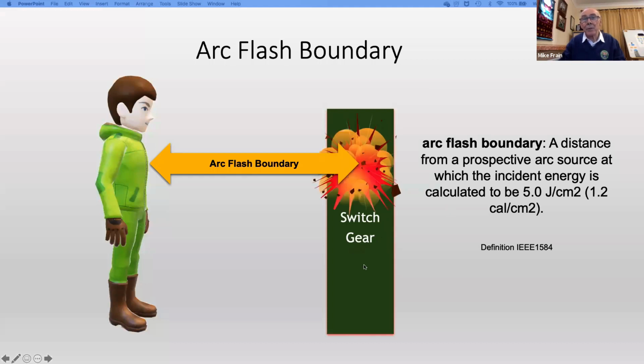And then I mentioned arc flash boundary. What's this? This is quite a good and important measurement, actually. From IEEE 1584, an arc flash boundary is a distance from a prospective arc source at which the incident energy level is calculated to be 5 joules per square centimetre or 1.2 calories per square centimetre, that magic figure, onset of a second degree burn, if you remember from my earlier slides. That's what an arc flash boundary is. It has a particular meaning within US consensus standards, but what it means is that stood outside the arc flash boundary, there should be no injury whatsoever. Stood inside the arc flash boundary, we've got to start thinking about other measures to protect the person.